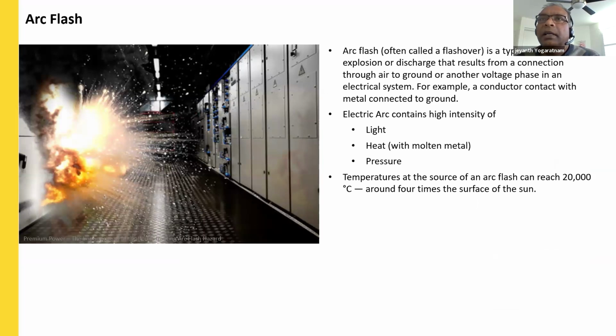The other factor, another application with the feeder relay, is arc flash protection. What is arc flash? Arc flash is a type of electrical explosion or discharge that results from a connection through an arc to ground or another voltage phase in the electrical system. For example, a power conductor coming into contact with a metal connected to the ground will create an arc flash. The arc will create light energy, excessive heat energy, as well as pressure. The temperature at the source can go up to 20,000 degrees Celsius. It is almost 4 times the temperature of the surface of the sun.